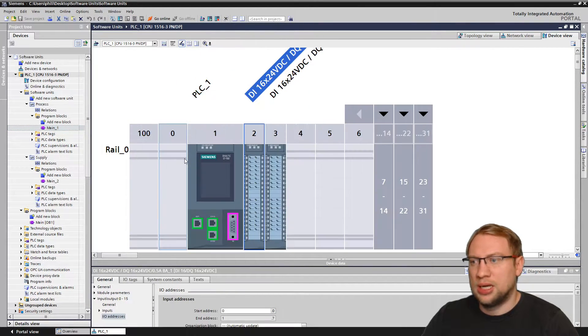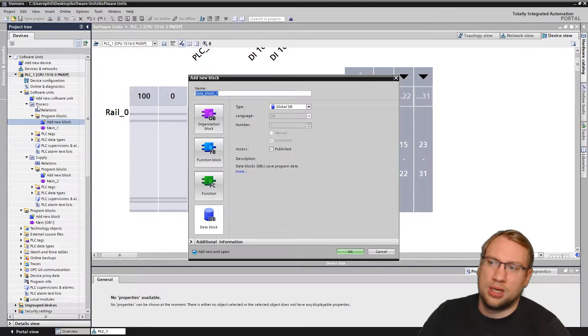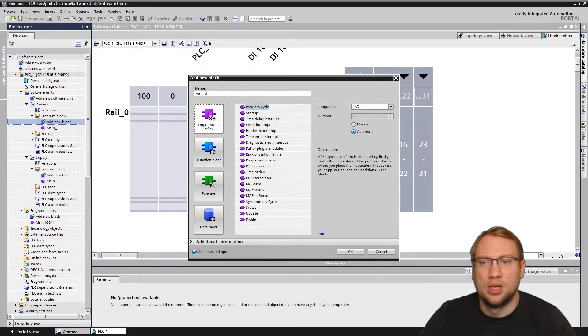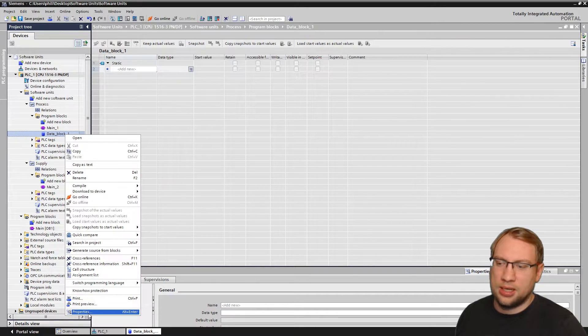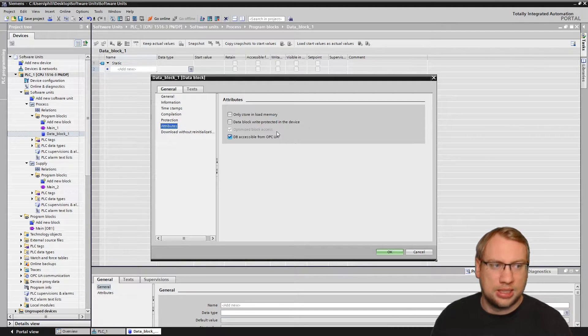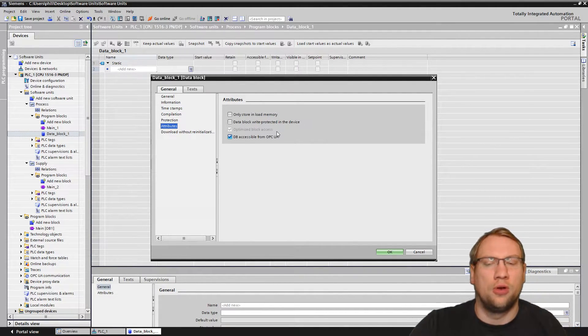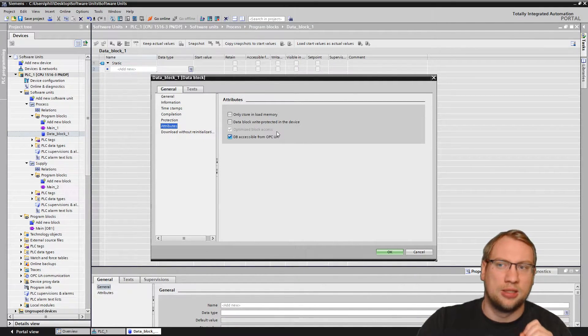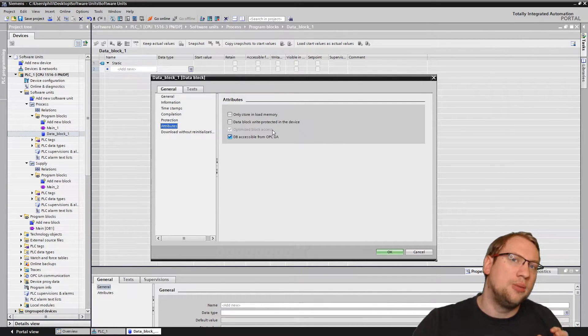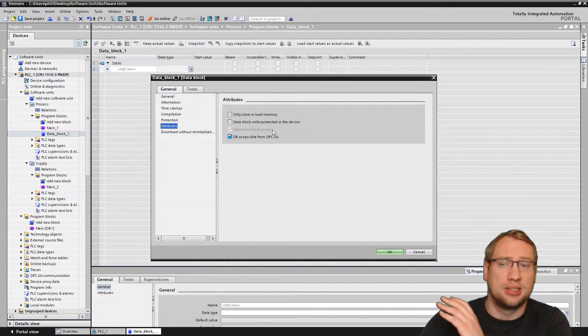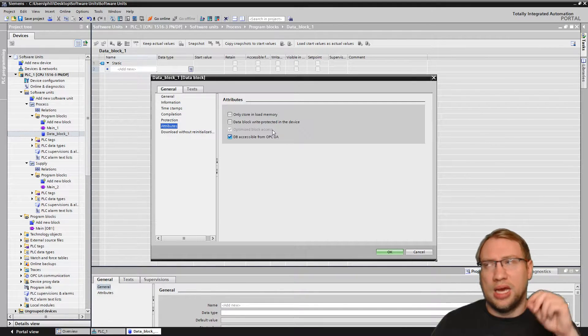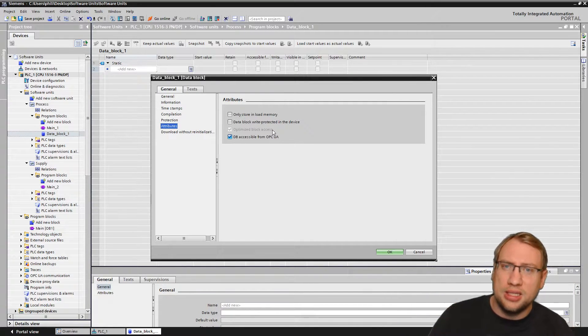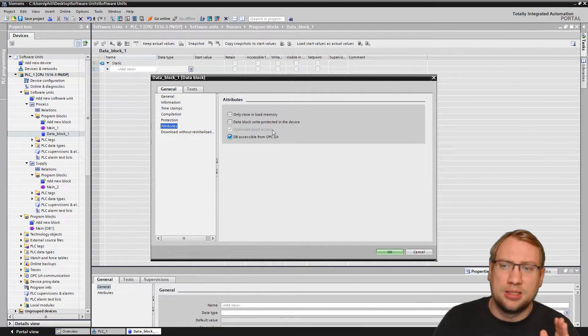The first important restriction is the following. If I have a new block — I'm now inside my process software unit — when I create a block, it doesn't matter which one I select. Let's make a data block, for example. If I right-click and look into the properties, under attributes, the optimized block access is on for all of them. If you have optimized block access active, that means you cannot work with addresses anymore — everything works with tags and name-based only.